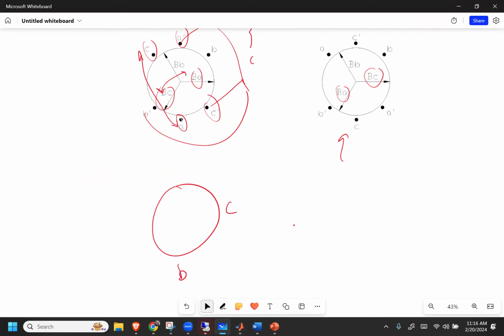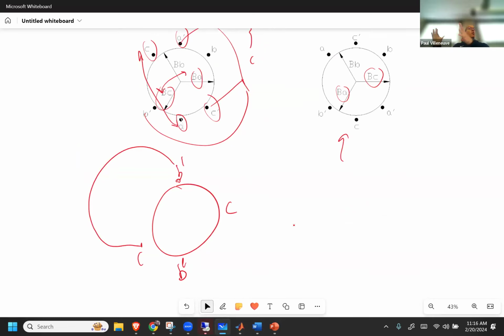So I still am going to swap B and C prime, because remember what happens is this is coming out of the motor. It actually only, if you connect over here, it only connects externally, at the motor junction box. So literally on the side of the motor you have 6 leads coming out of the actual casing of the motor, but then you connect those 3 phases at that location, at a common point. So here's B and C prime. And then, oh...